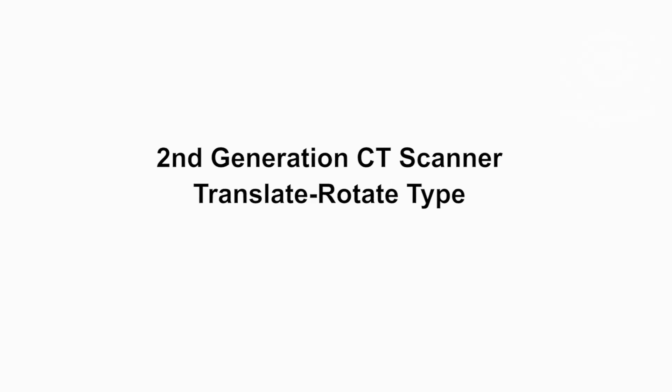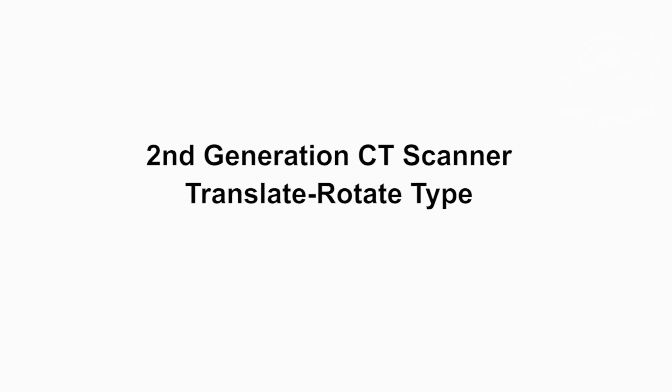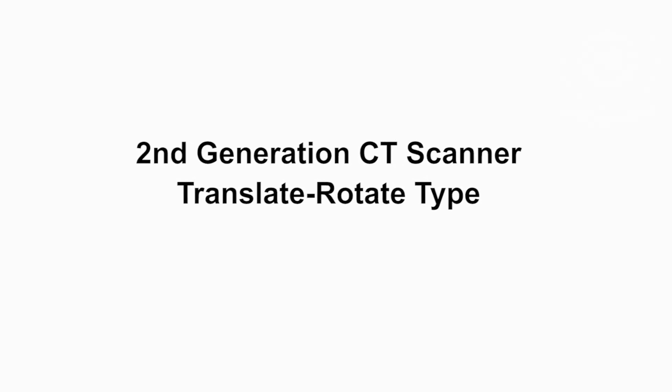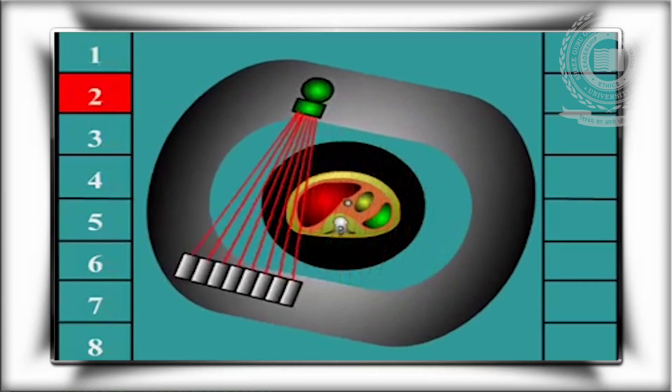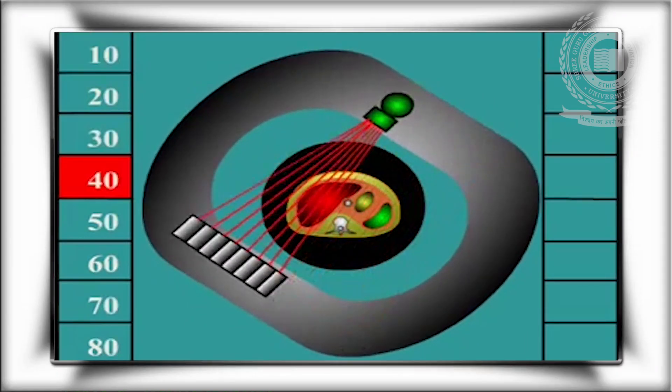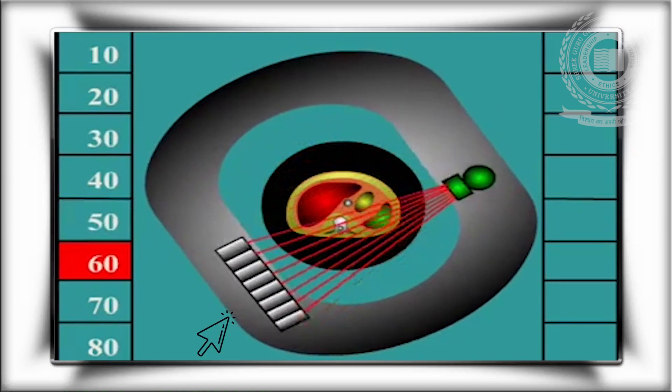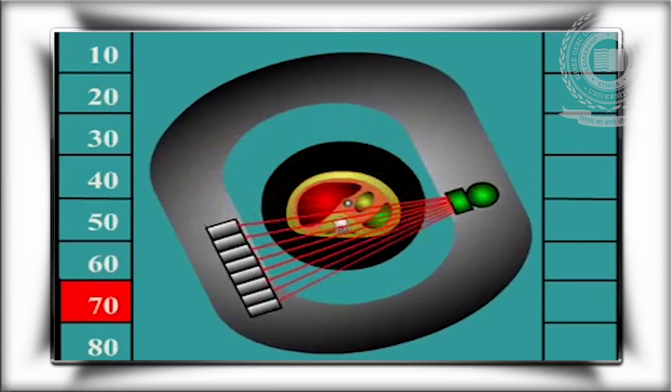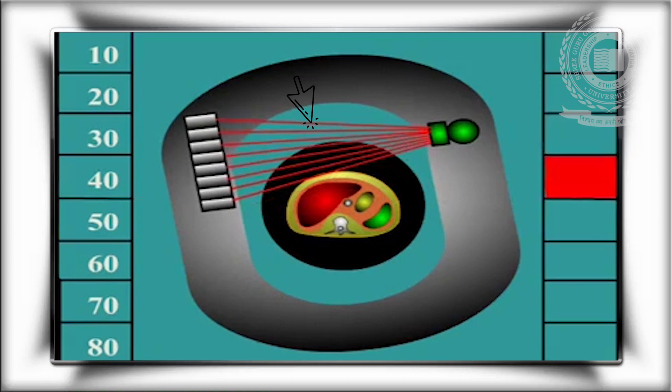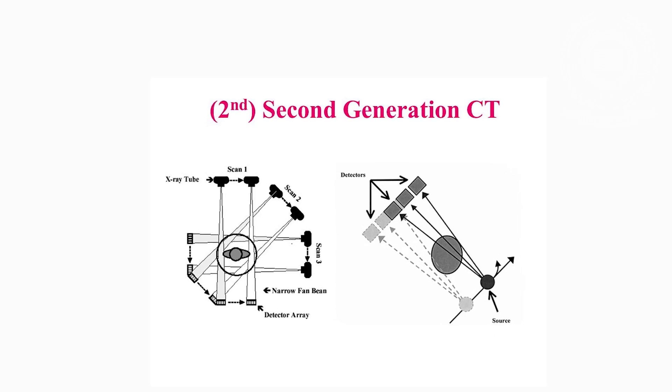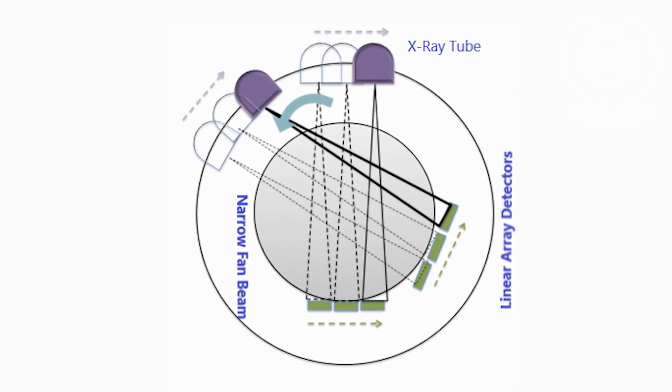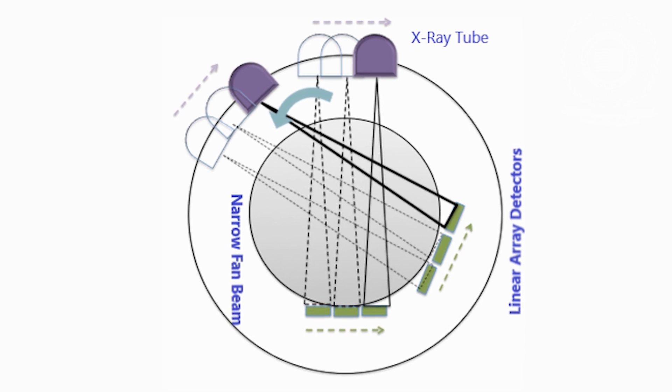Now we come to second generation. This generation was almost similar to the first generation, that is translate-rotate type, but the new feature of this equipment was the use of multiple detectors in a linear geometry and narrow fan beam of X-rays. Due to multiple detectors and narrow fan beam of X-rays, the image quality got improved.